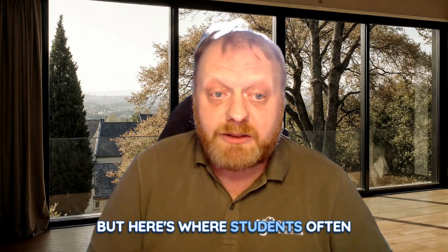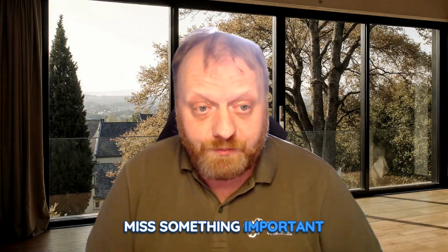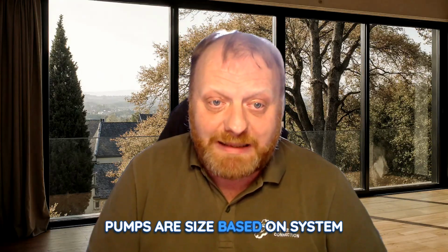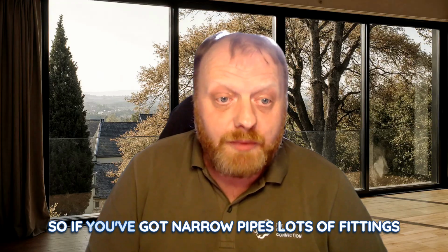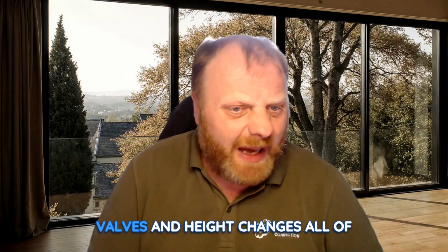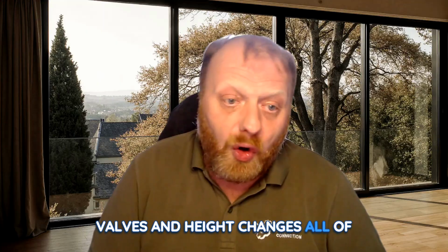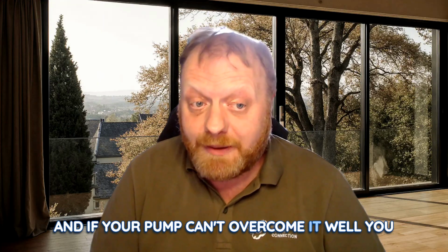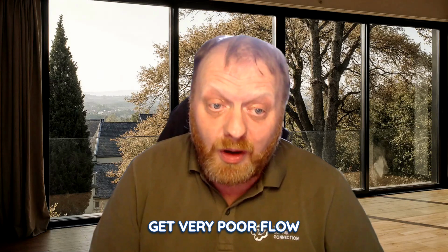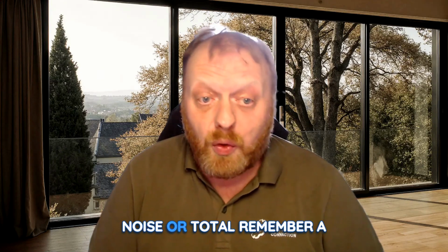But here's where students often miss something important. Pumps are sized based on system resistance, not just distance. So if you've got narrow pipes, lots of fittings, valves and height changes, all of these add to resistance. And if your pump can't overcome it, well, you get very poor flow, noise or total failure.